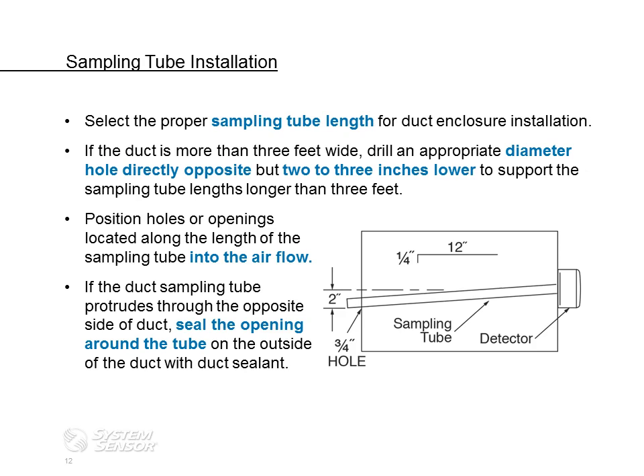Next step is to position the holes or openings located along the length of the sampling tube into the airflow. We need to make sure it's facing into the airflow so it'll draw that appropriate amount of air across the duct detector head. If the duct sampling tube does make a penetration through the far side, it's very important that you make sure that the red cap is in place and that any openings are properly sealed. It has to be sealed completely, so you don't allow air to escape out of the penetration.